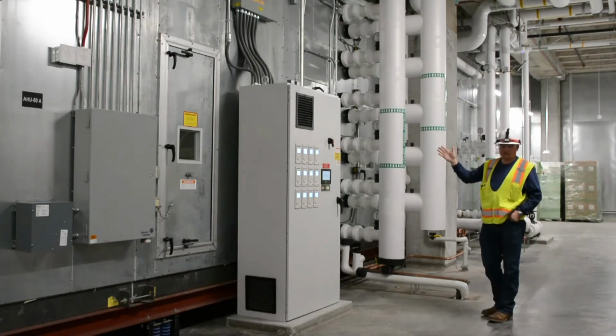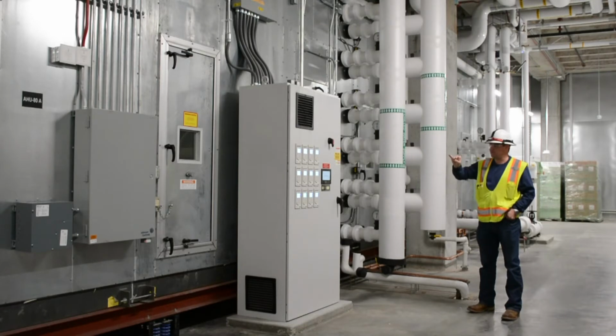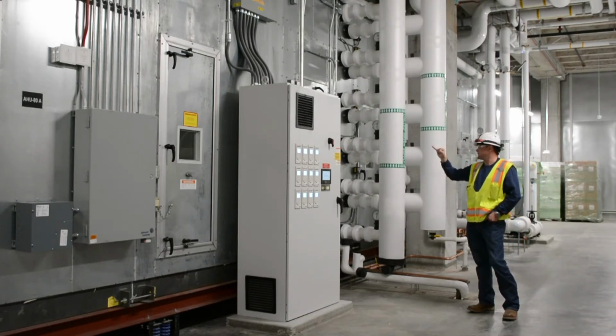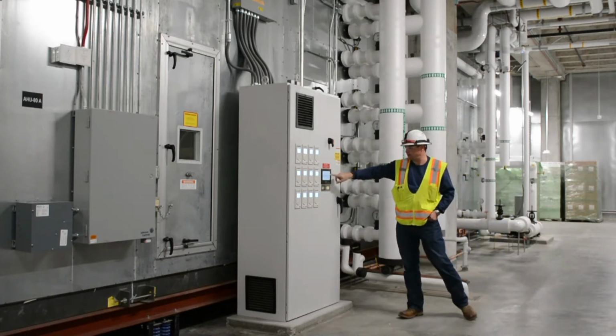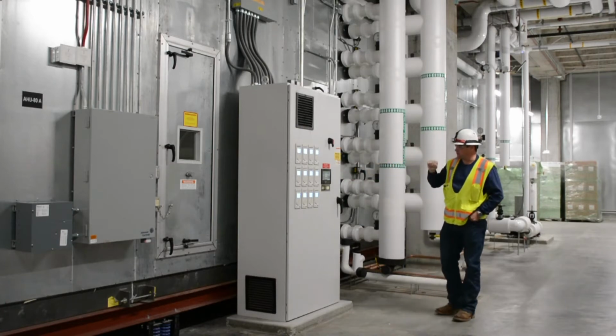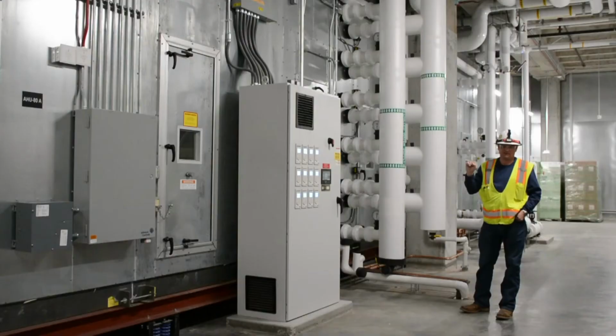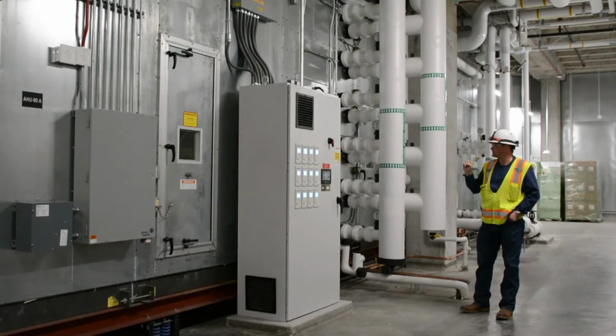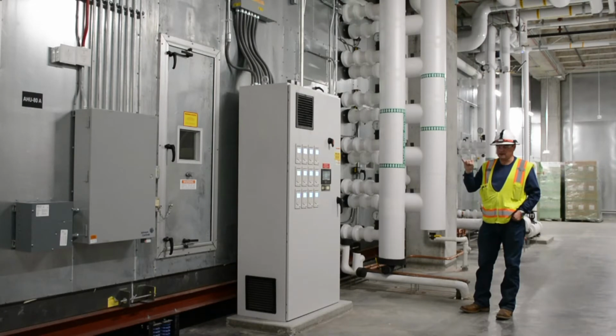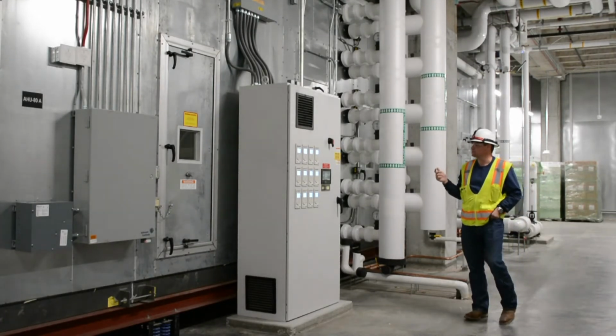The next section is our fan section. There's barometric backdraft dampers on each fan. This is a 12 fan array. Any given fan that does fail, you will be able to see that on your Paragon, and it'll report an alarm, and it'll flash red that one individual fan is not reporting any CFM. It's a totalized fan array, so we are measuring CFM at each fan and adding them together for your total CFM value, or cubic feet per minute, that the fan's delivering.